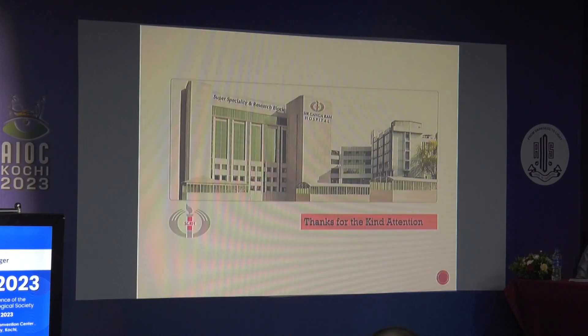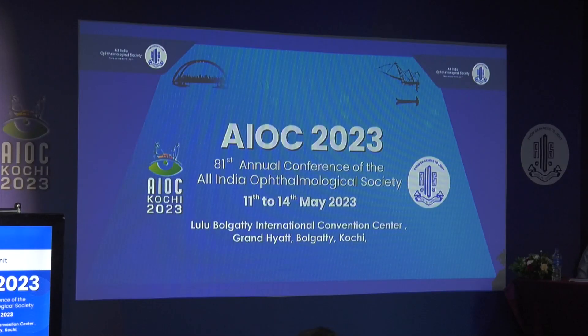In closing, the important points to consider: different machines have different protocols, so patients should be reviewed on the same machine using the same protocol. All OCT measurements are compared to normative data of Caucasian subjects, which must be considered. Actual placement of the measurement area should be checked and amended manually if needed — for example, when examining the optic nerve area, it should be properly centered, and you should manually correct any decentration, otherwise the values will be fallacious. Thank you for your kind attention; I am happy to answer any questions.